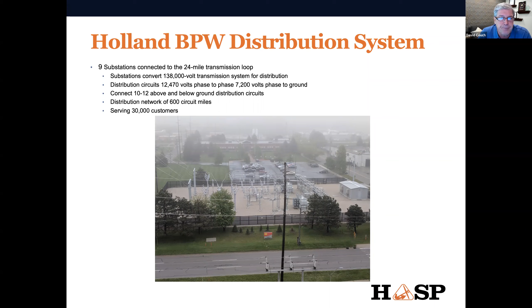So then how does it connect to the grid? This picture isn't of the actual place, but it's an example of a substation, at the corner of Lakewood and 112th. The transmission loop we talked about comes in and goes out, and there are 4 lines that come in from other parts of the grid: 138,000 volt lines from various parts to the south, one dedicated line from the J.H. Campbell plant, and another line from elsewhere in the grid.